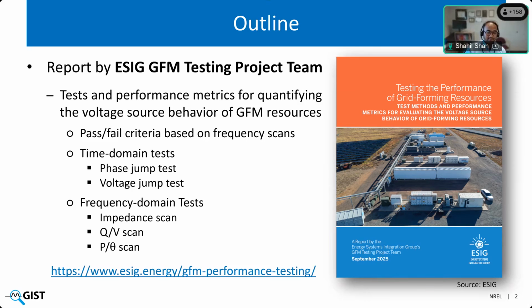We are covering pass-fail criteria based on frequency scans or frequency domain analysis, time domain tests, including phase jump and voltage jump, and frequency domain tests, including impedance scan or V by I scan, Q by V scan, basically what I call the reactive power scan, and then P by theta scan or active power scan. Here's the link for the report if you want to access it. I think Lacey will also put that in the chat box.